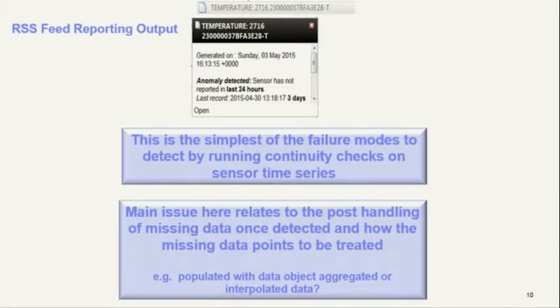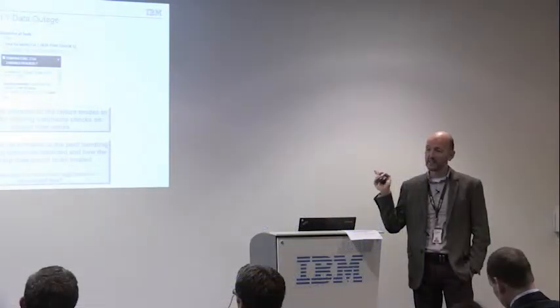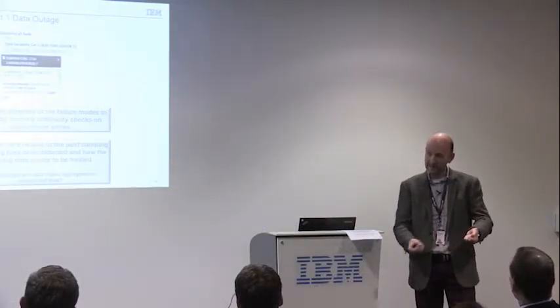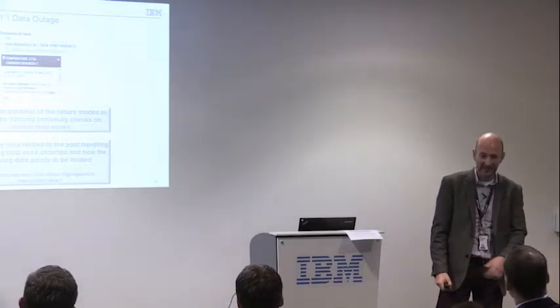So we look over the last 24 hours and it gives us the last date that it actually reported. So this is quite useful. It means we can go out there and address it. And in fact, we see that with our temperature sensors. We have temperature sensors in our office across the way, and they're underneath the desk and they're wired, and people are hitting off them all the time, so I go in and say, oh yeah, that's that sensor, go down and just plug it back in.